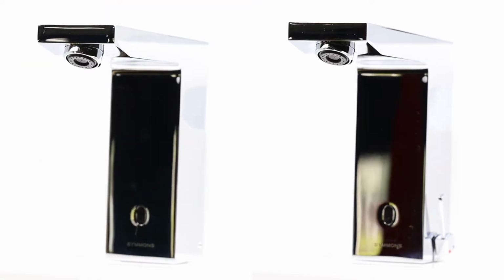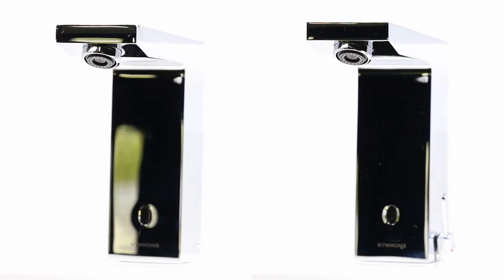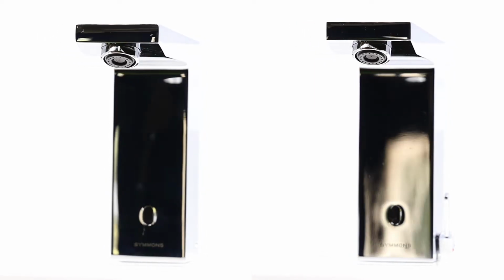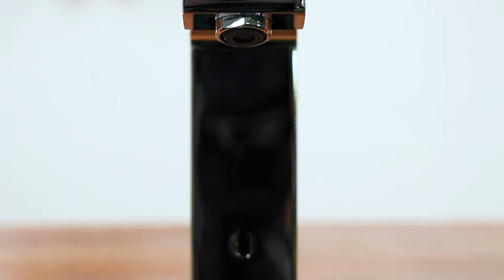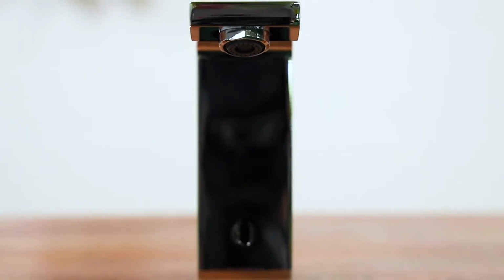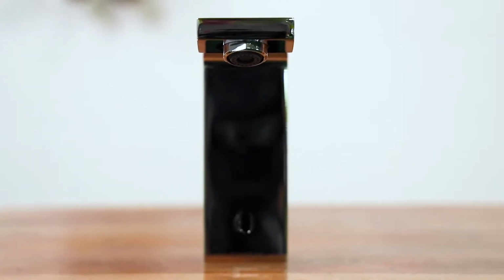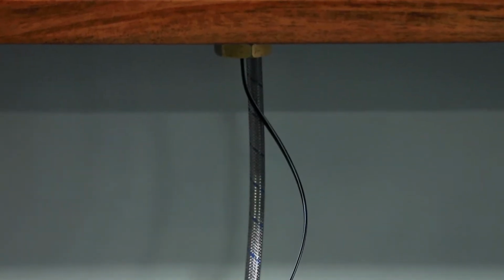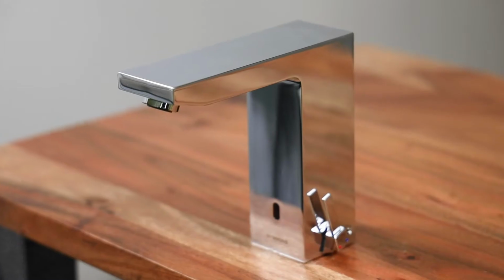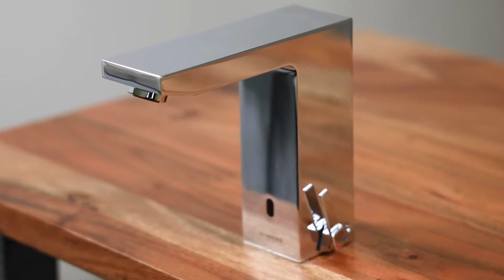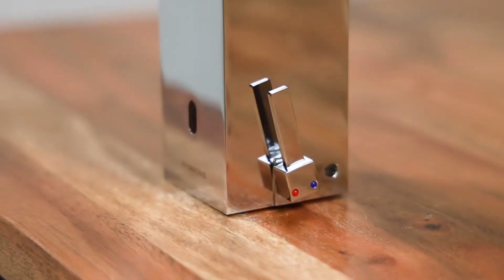The Duro ActivSense faucet is available in two configurations, depending on how your tempered water is delivered. The S6360B is a standard single supply version, which is usually used for situations where only tempered water is supplied to the faucet. The water is usually tempered through a TMV, which is a thermostatic mixing valve. The S6360BM version has a manual temperature mixture lever on the side. This version has separate hot and cold supply lines.